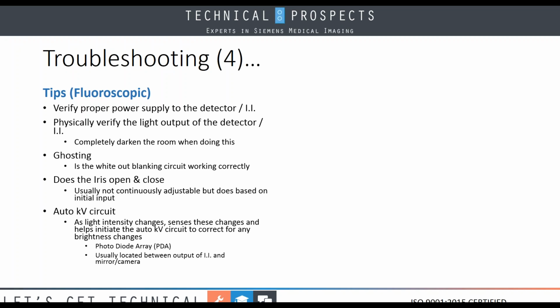Well, when we got all these little transistors in these detectors, we've got a similar factor in there. We have to flash it. So that helps remove ghosting. If you're seeing double images, you need to start possibly thinking about, is that blanking or flashing circuit working correctly? The iris opening and closing. The iris typically presets in the fluoro mode off the initial pulse. It's not something that's opening and closing all the time.